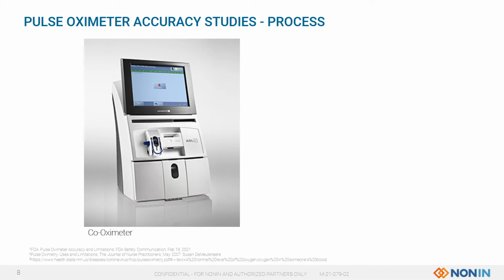So the true gold standard for saturation is measured on a co-oximeter. And this is a picture of a co-oximeter and a blood gas analyzer. So pulse oximeters are calibrated against an invasive blood gas machine or co-oximeter to determine accuracy to standards and regulatory claims. And a co-oximeter does require a blood draw.